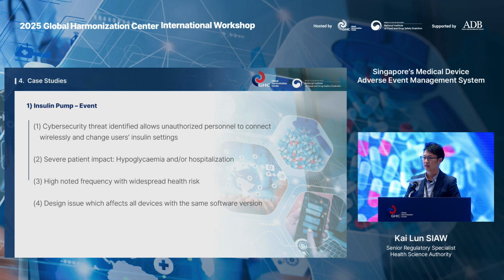The first case study is on an insulin pump. We received the first adverse event, which was a cybersecurity issue that the insulin pump had. The insulin pump is carried around with the patient, and it automatically injects insulin into the patient at a certain time. What happened was there was a cybersecurity threat that allowed unauthorized personnel to connect wirelessly and maliciously change the insulin settings on the pump. The patient impact would be either increased or decreased insulin, leading to hypoglycemia and probably hospitalization if the patient did not realize.